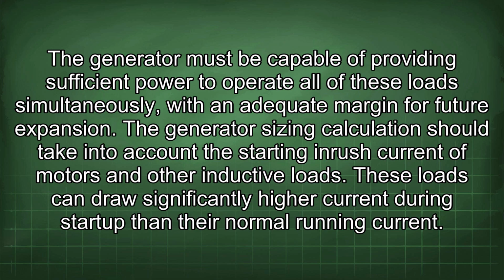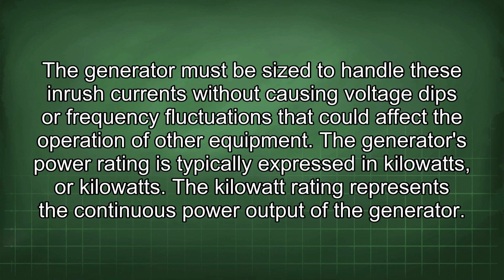for future expansion. The generator sizing calculation should take into account the starting inrush current of motors and other inductive loads. These loads can draw significantly higher current during startup than their normal running current. The generator must be sized to handle these inrush currents without causing voltage dips or frequency fluctuations that could affect the operation of other equipment.